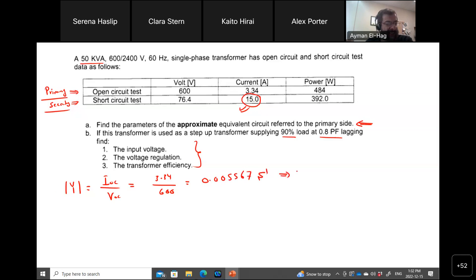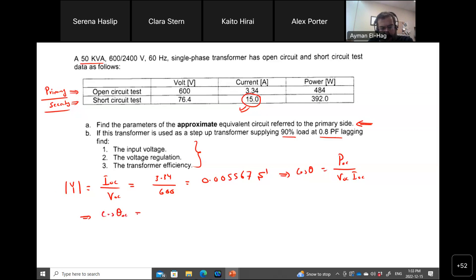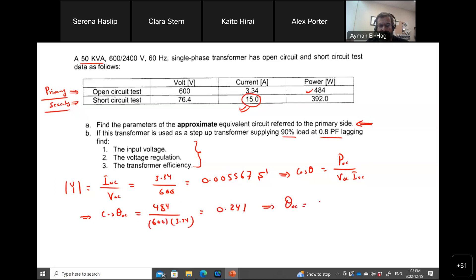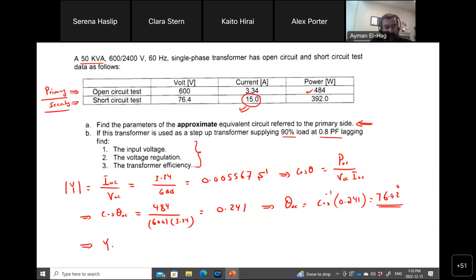That gives Y equal to 0.005567 Siemens. From this we can also find the angle: cosine theta equals P_oc divided by (V_oc times I_oc), so cosine theta_oc equals 484 divided by (600 times 3.34), which gives 0.241. Therefore theta_oc equals cosine-inverse of 0.241, which is 76.02 degrees. So Y equals 0.005567 at an angle of minus 76.02 degrees, because this is an admittance — the opposite of impedance.